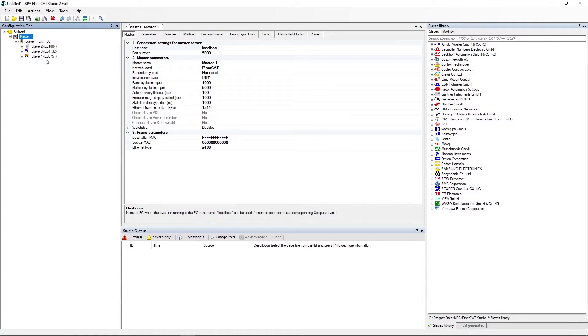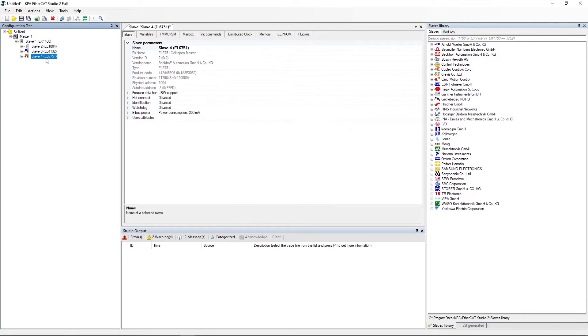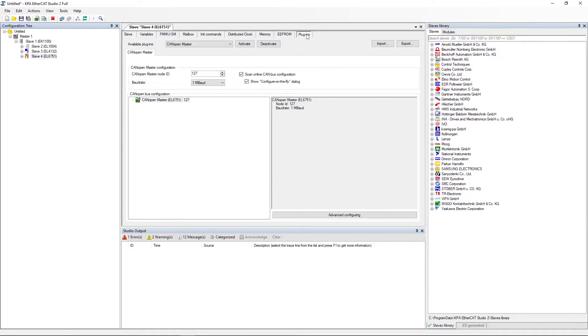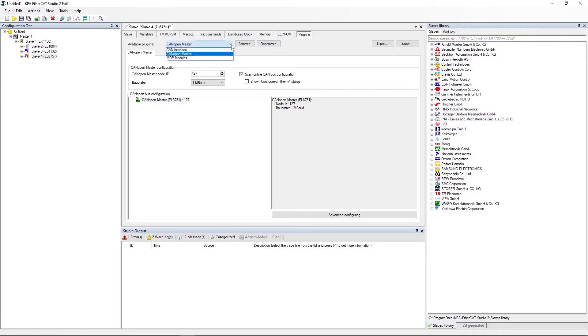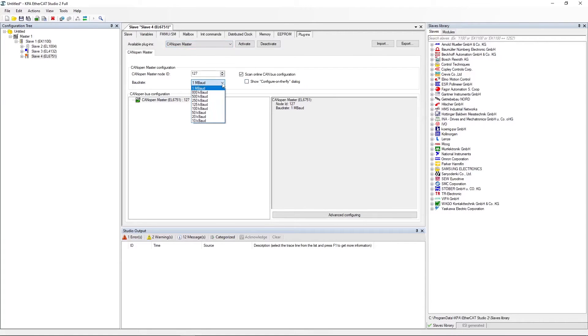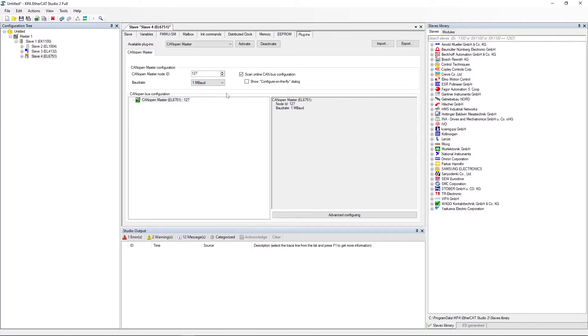Select the EL6751 slave, go to the Plugins tab. Scan online CAN bus configuration checkbox should be set. Disable the show configure on the fly dialog checkbox. In the available plugins field, select CANopen master. Set baud rate that corresponds to the baud rate of physical device connected to EL6751. Attach the master.